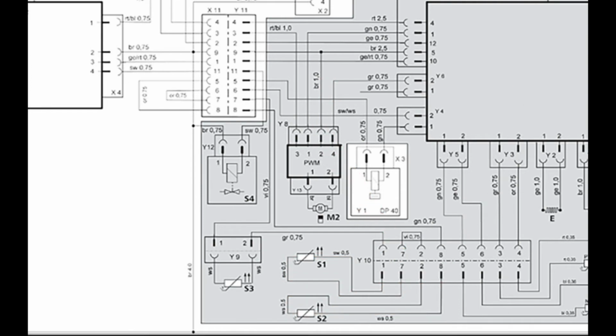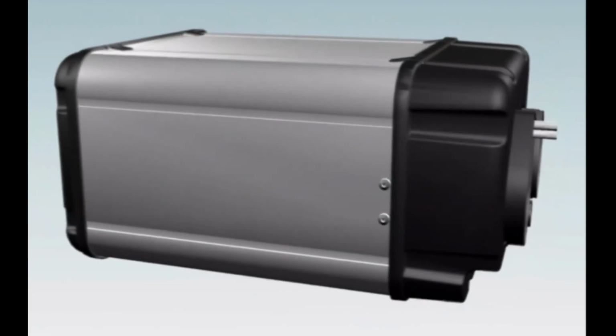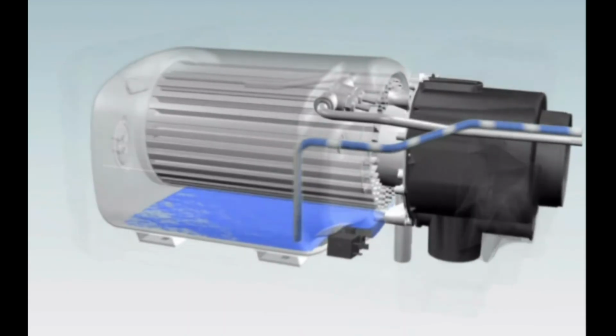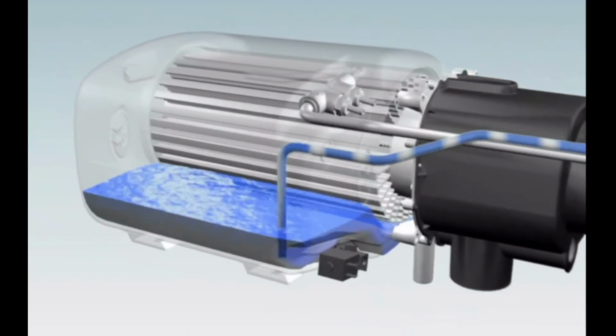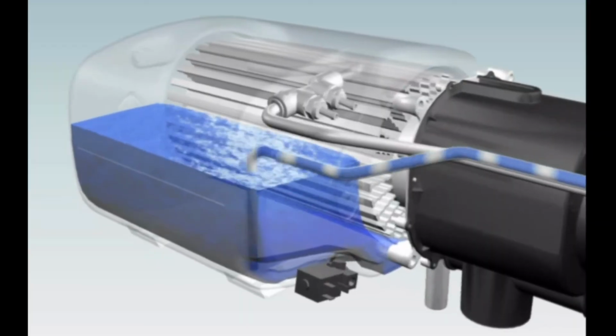Don't forget, you've been doing this testing on the switch side of the harness, the male connector housing. On the female connector housing, there is a short jumper wire between pins 7 and 2 of the internal harness. This needs to be checked as well. If the switch harness assembly needs to be replaced, the boiler tank will have to come out of the case. Now, let's talk about the water side of things.